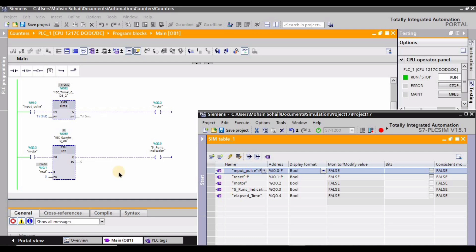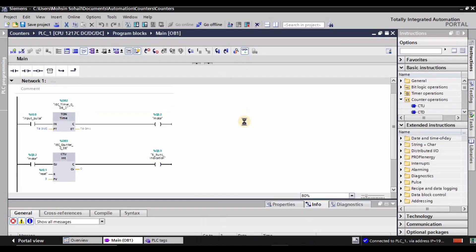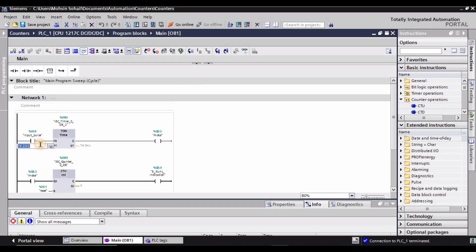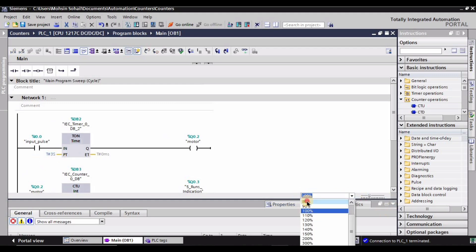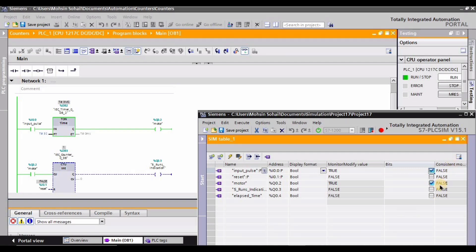I'll adjust this window so I can see the logic at the same time. When I provide the pulse to the timer it must hold for three seconds and then the motor should turn on. As you can see, when I give the input pulse it is not holding for three seconds because of the earlier mistake — I need to type 3000 for three seconds. So I'm correcting it to 3000 milliseconds, downloading the program again after correcting the mistake, clicking Load, and turning on monitoring mode again.